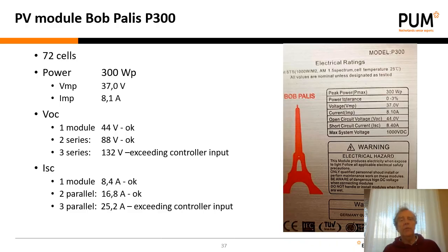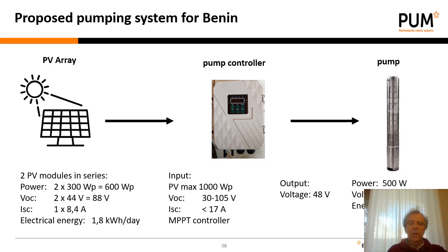But you see, if we would have 3 of these panels in series, we would exceed the controller input voltage. And if we look at the current, one module could max deliver 8.4 amps. So that will be okay. If we put 2 in parallel, we would have 16.8 amps, also still within the specs of the controller that we just saw. And if we put 3 in parallel, we will exceed the maximum current input for the controller. So here you see the system as we proposed for Benin. We had 2 PV modules in series, total 600 watt peak. We have the MPPT controller that we presented, and we had a positive displacement pump.